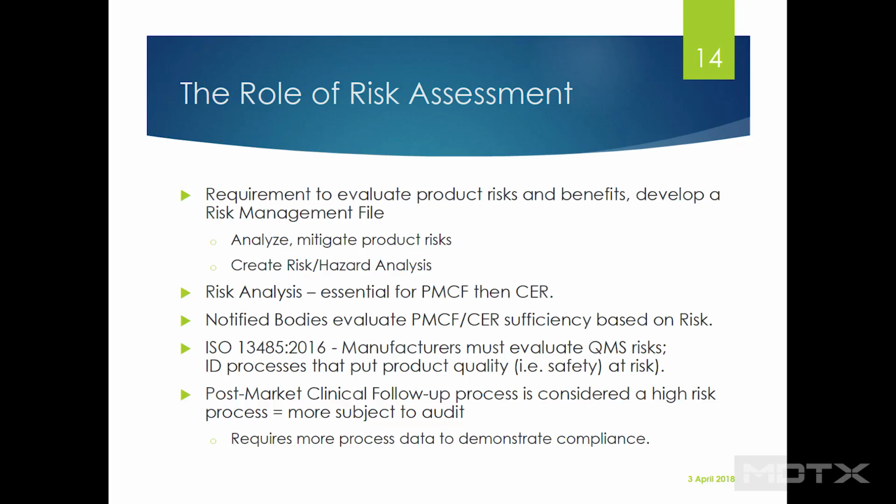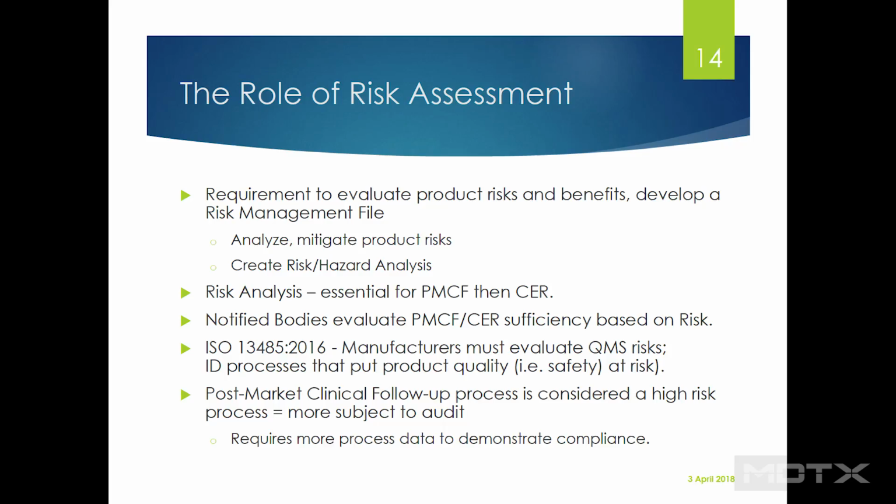And they're also, manufacturers have to evaluate risks in their own quality management system, identify processes and process risks that put product quality and therefore safety at risk. That's another one of those 13485 changes I was talking about. The emphasis of not just product risk management, but process risk management, and that's a big shift. And of course, everything around post-market clinical follow-up is considered high risk.